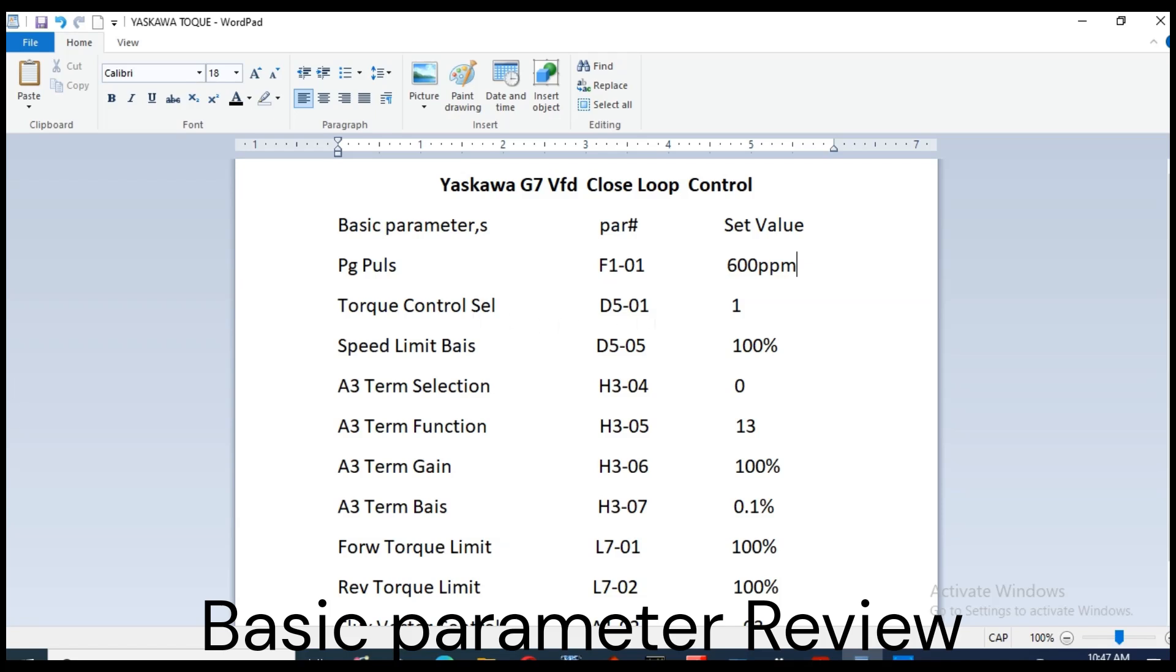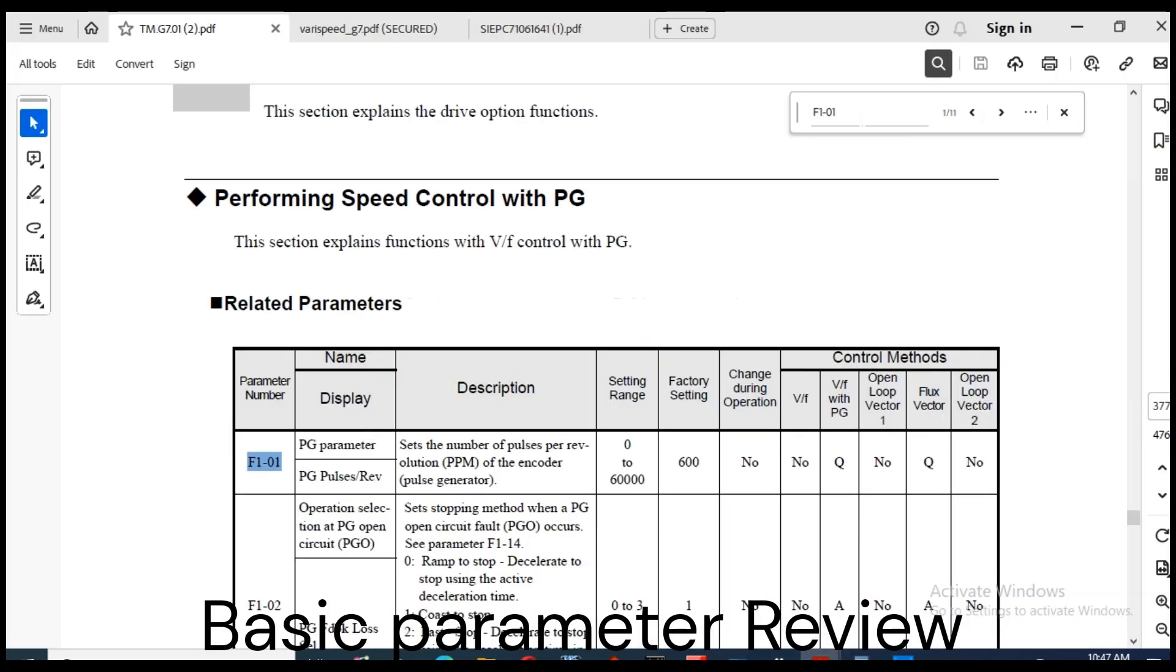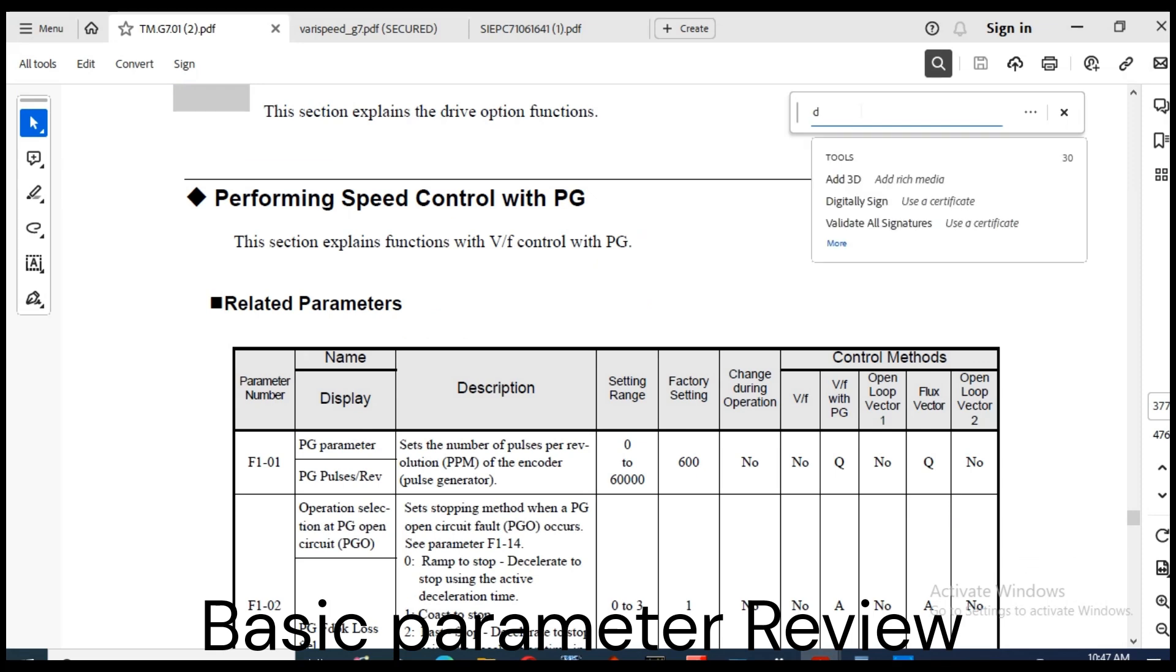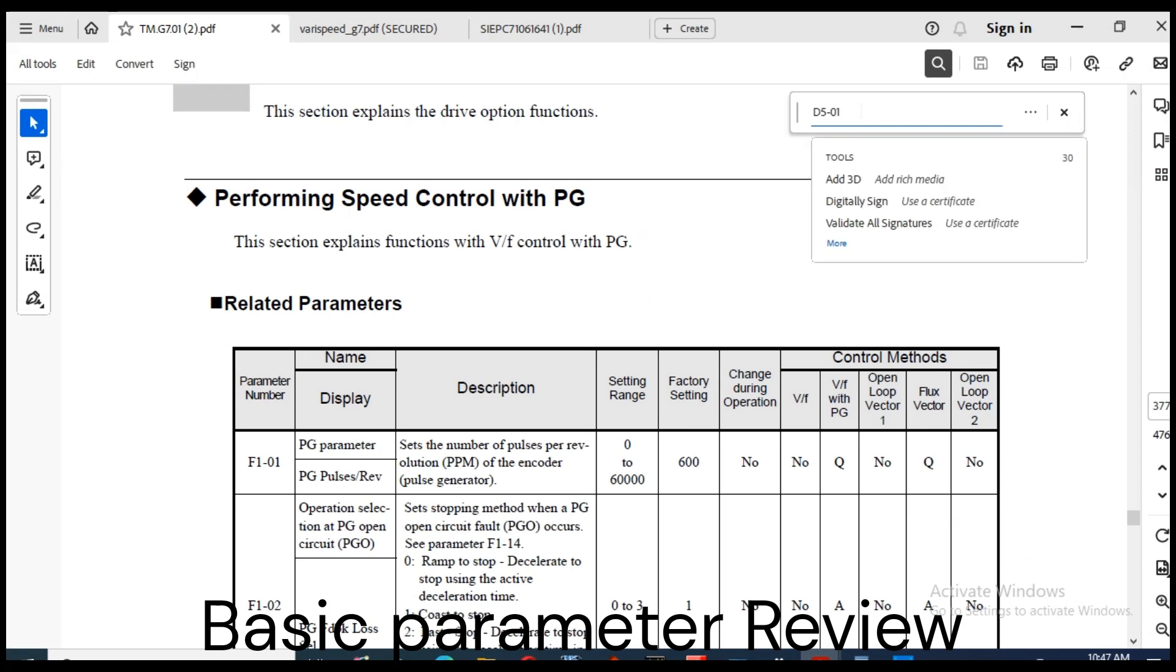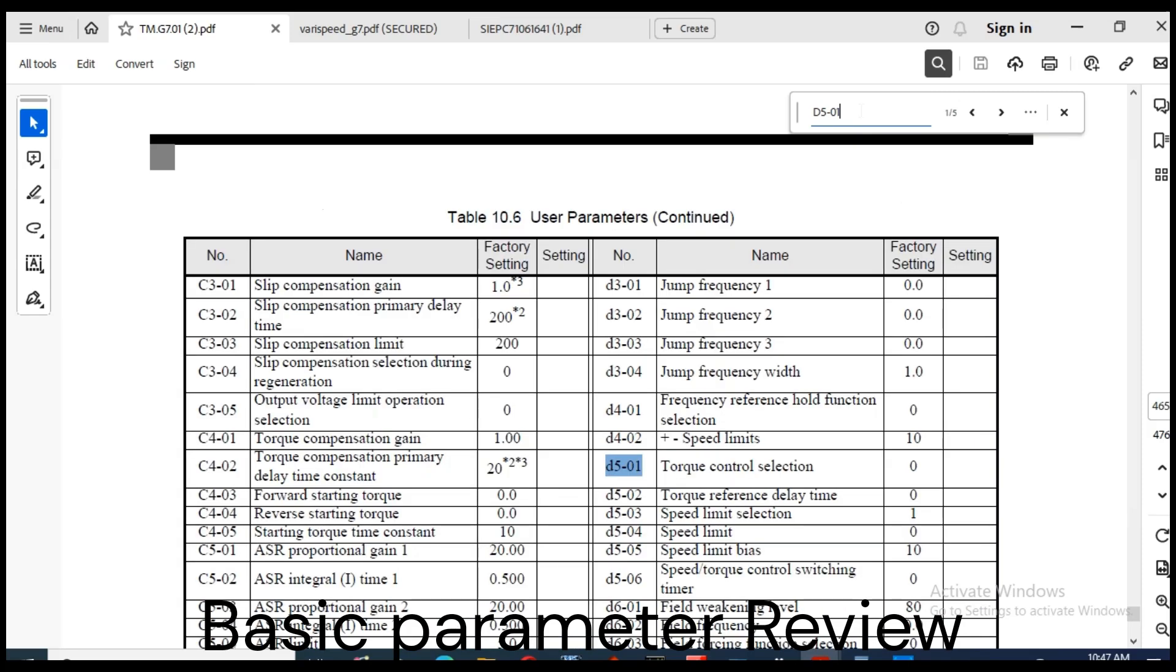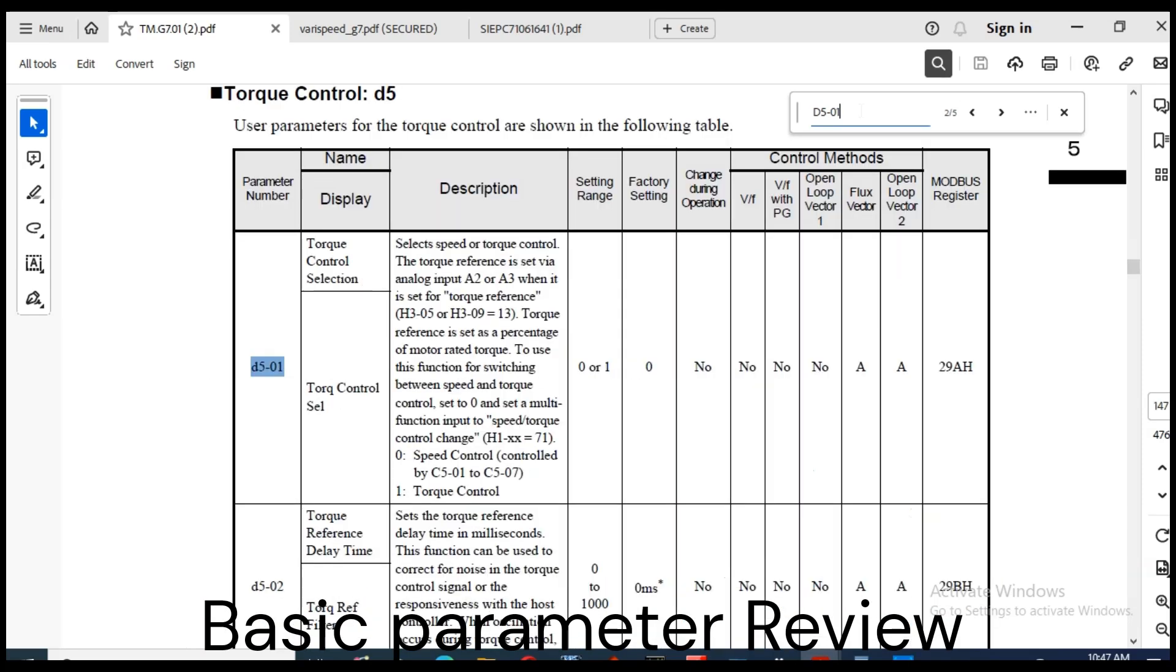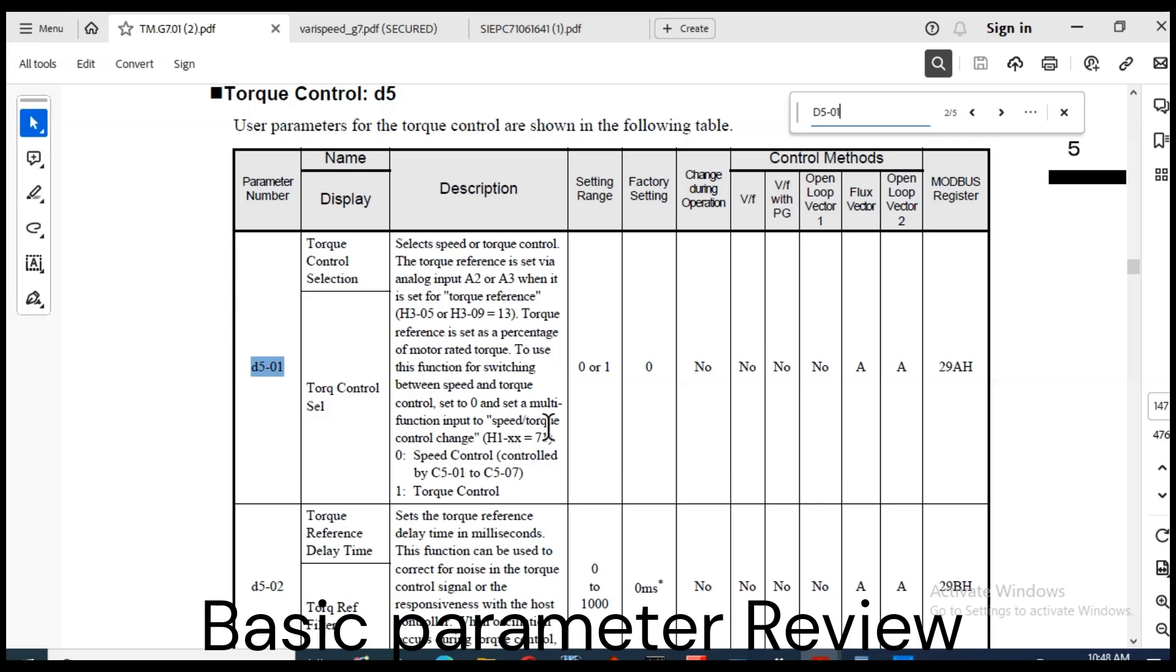Now we set torque control selection. D5-01 torque control set selects speed or torque control. The torque reference is set via analog input A2 or A3 when it is set for torque reference. H3-05 or H3-09 equals 13. Torque reference is set as a percentage of motor rated torque to use this function.